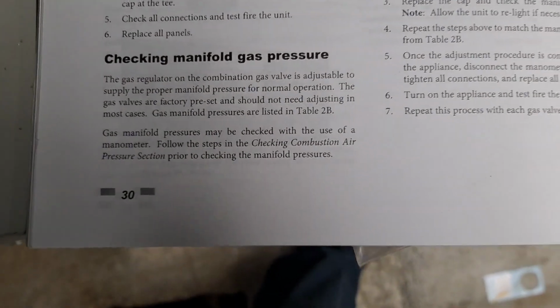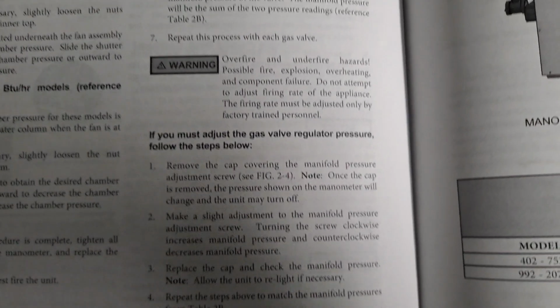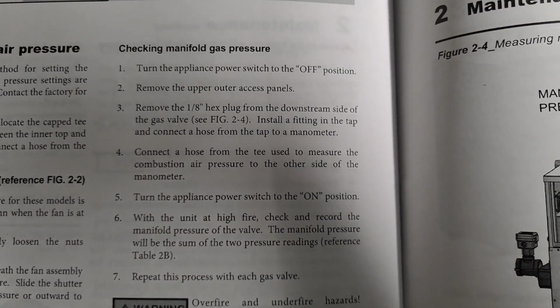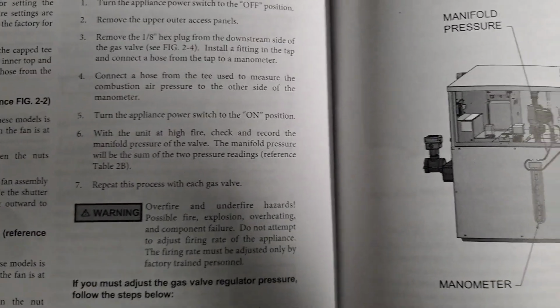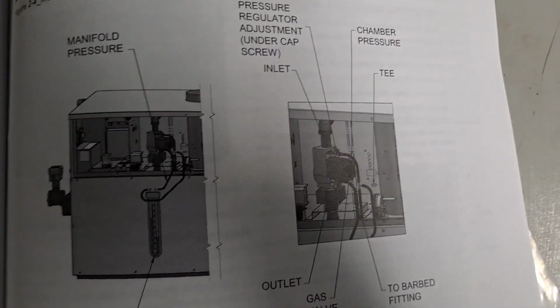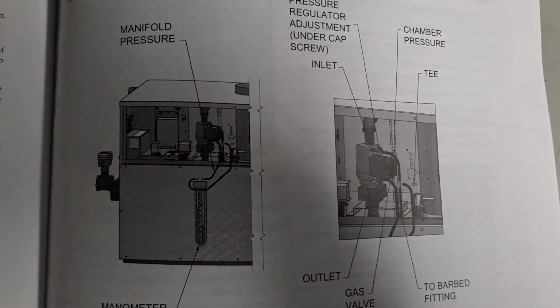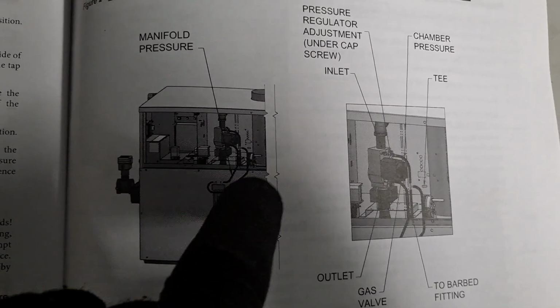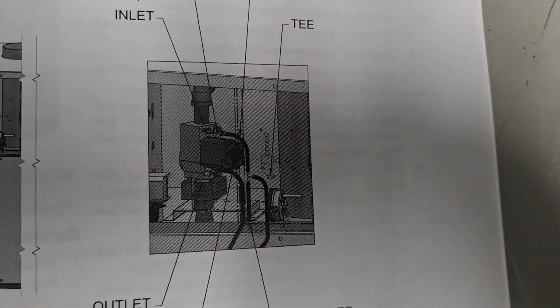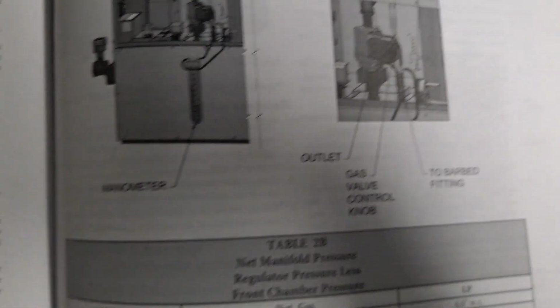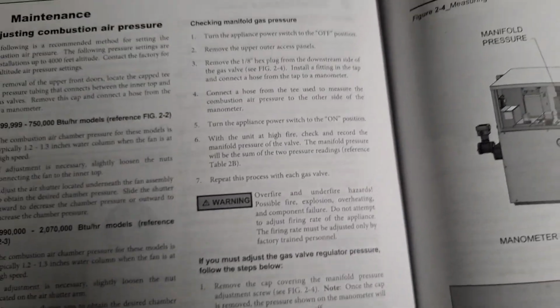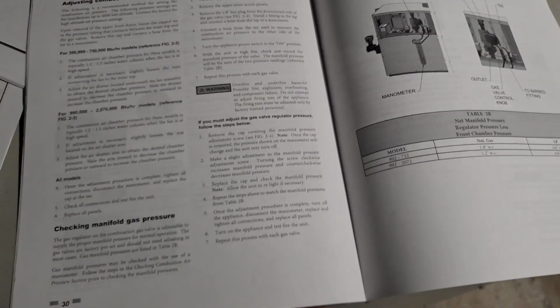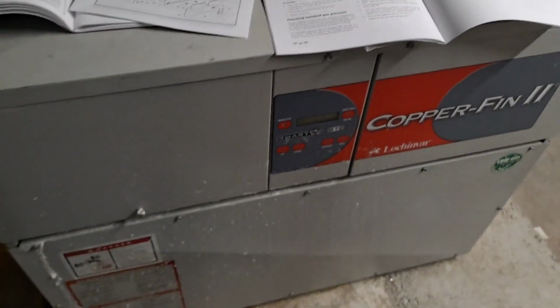And then I'm doing this, so checking manifold pressure here. So there is the rest of it. And they give you a good little diagram here, so you can see you're on that T, you're on the gas valve. Same thing here, and you're using differential pressure between the two, so that's between chamber and manifold, and that is how you set your gas pressure on these boilers.